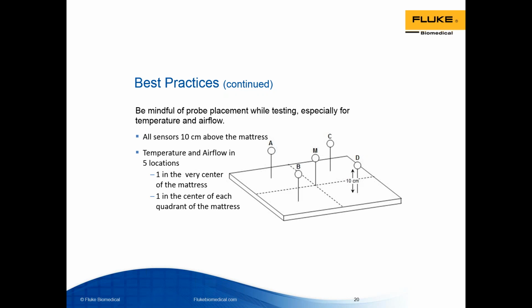So if we were to divide the mattress into 4 equal quadrants, temperature and airflow probes would be placed in the very center of the mattress, which is point M on the diagram you see, and then also in the center of each quadrant, so points A, B, C, D on your screen right now. Finally, the pattern of airflow just slightly differs in every model of incubator. So it's important to be familiar with the direction of that airflow inside the model of incubator that you're testing and place the airflow probe properly to make sure you're getting an accurate measurement.